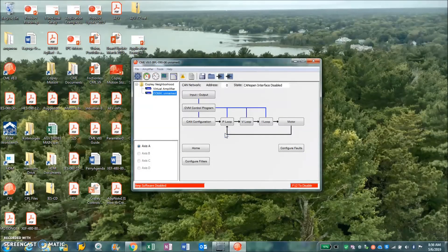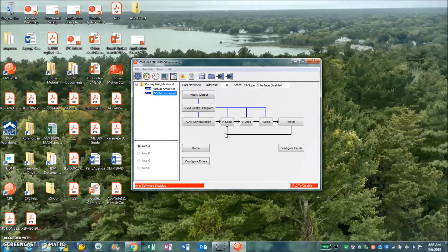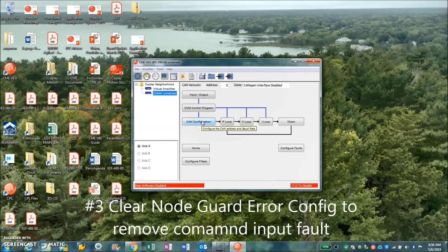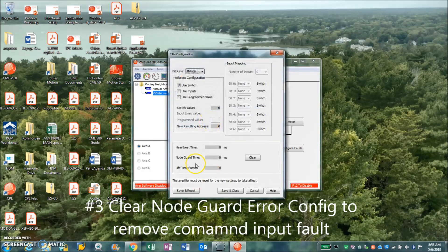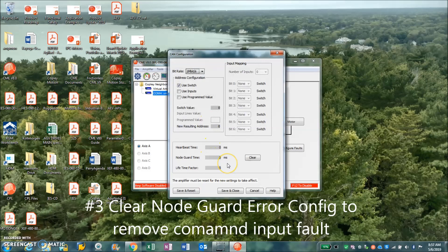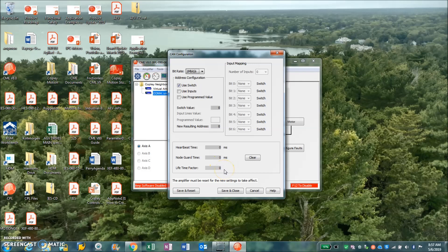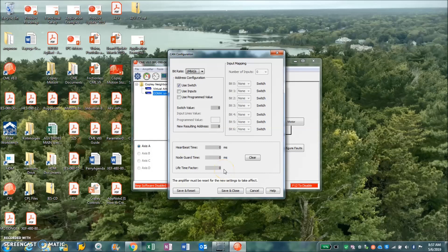Number three: there's something new on the network configuration. I get a lot of support calls for why do I have command input fault, why did I configure the node guarding when I never entered anything for that. But if you use some CAN open master software and then you save to flash, the node guarding - of course these values will be there and the drive will node guard because it's saved to flash.